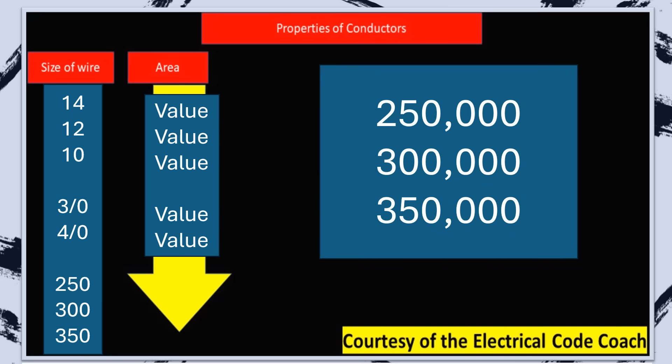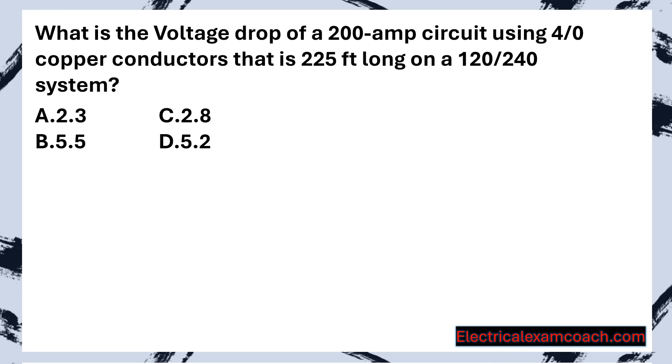So we have 250,000, 300,000, 350,000. Once you get past 4/0, you're going to get into 250, 300, 350,000, and all you have to do is add on the three zeros. What is the voltage drop of a 200-amp circuit using 4/0 copper conductors that is 225 feet long on a 120/240 volt system?